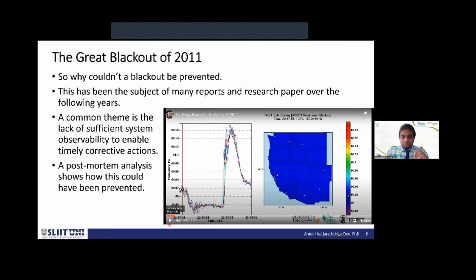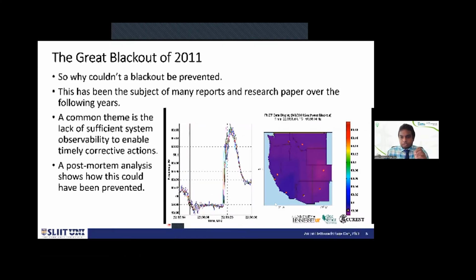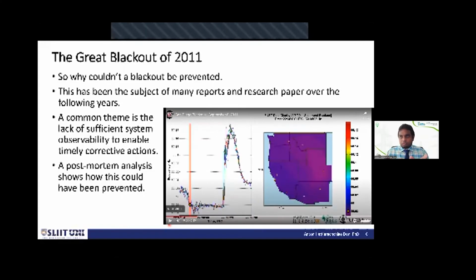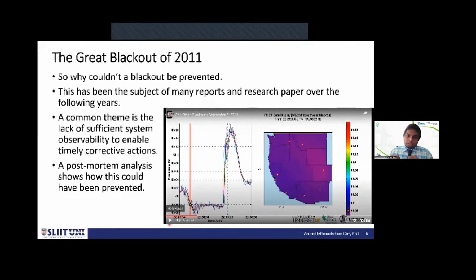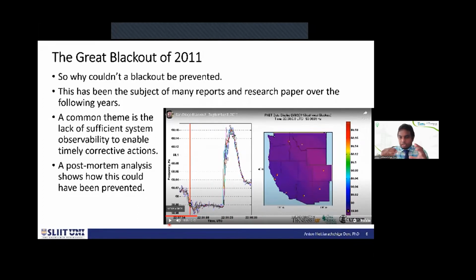Within a few seconds, there's a drop. You can see where the drop started, down south, southeast of this map. The system-wide frequency drops. Why? Because now there is an excess of load and not enough generation. That power line went down, so there is not enough power coming into this area, but the load is as it is. The system frequency drops and stays at that low value, 59 something, for quite a while.